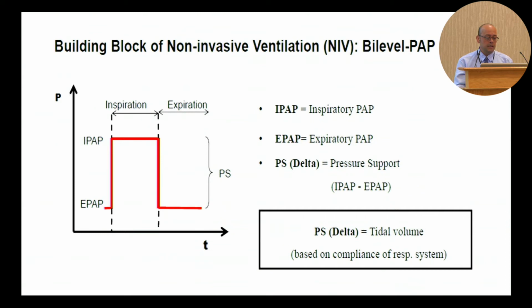And this is what we were talking about. So here is the pressure support. The wider your gap between the EPAP and IPAP, the higher your pressure support, the higher your tidal volume. And again, we're talking that these patients need ventilation. So most of the algorithms are going to tell us that the gap between IPAP and EPAP should be at least 10 centimeters of difference. If it's less than 10 centimeters, the tidal volume is going to be very reduced. Probably you're not going to be able to get rid of any CO2.